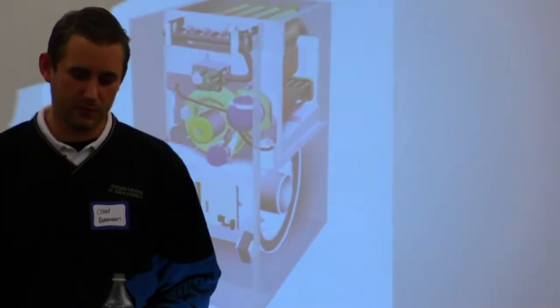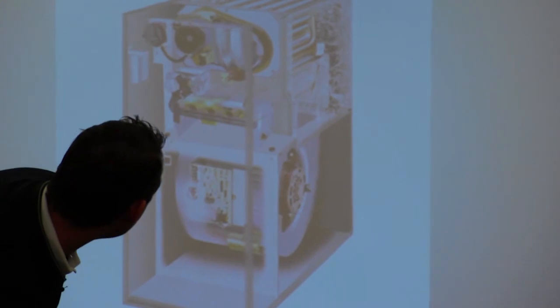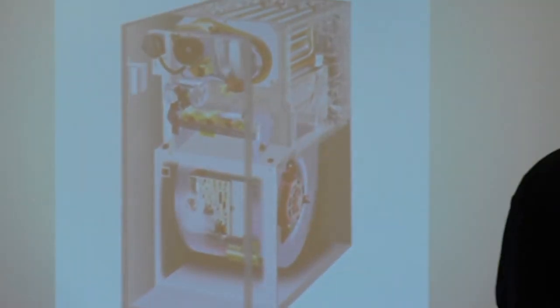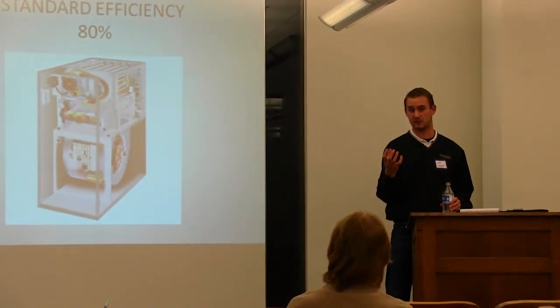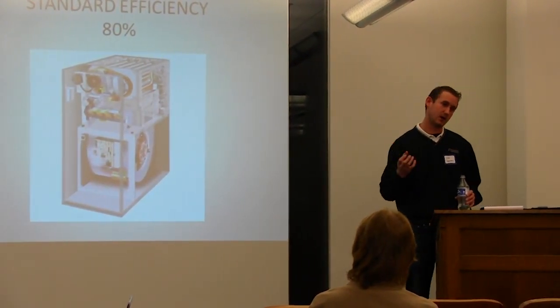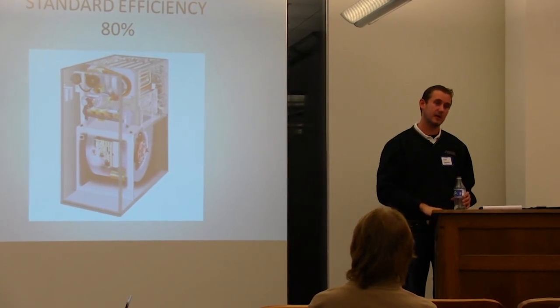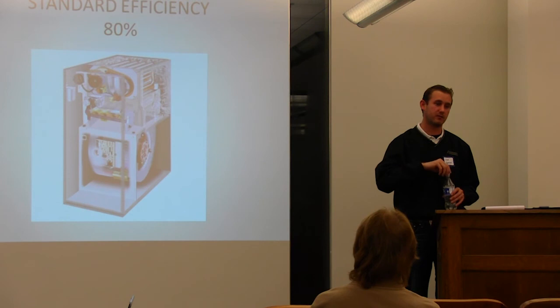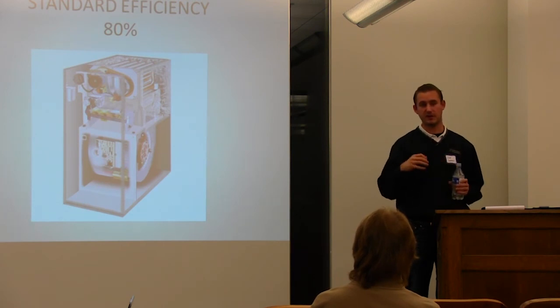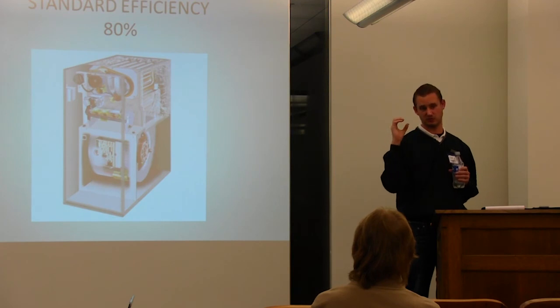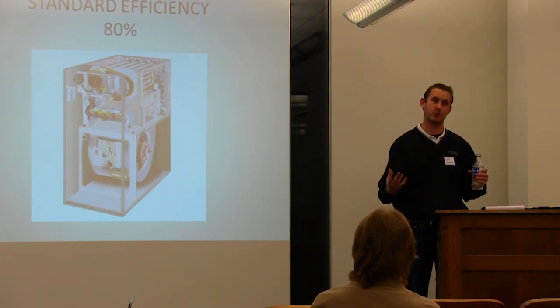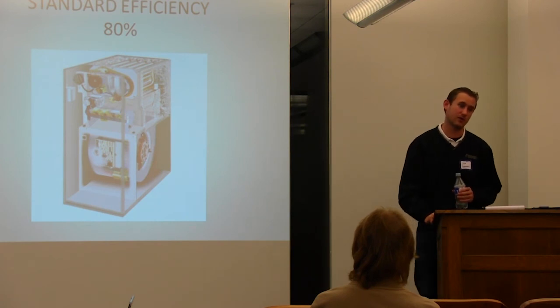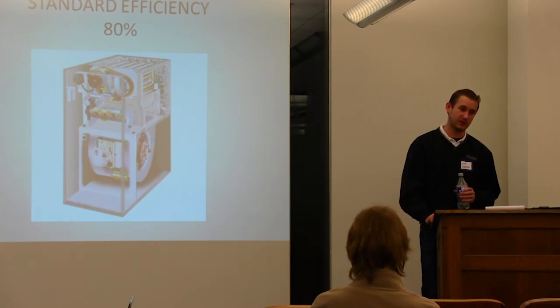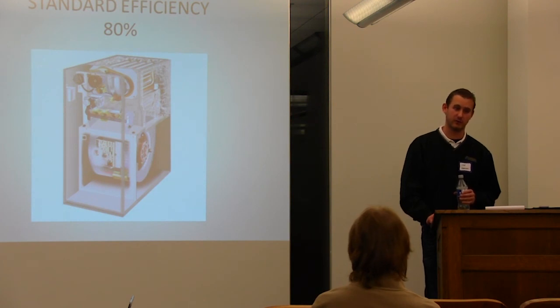That is the difference between an 80% furnace and a 90% furnace. An 80% furnace lacks a secondary heat exchanger, so only 80% of the heat is actually staying in the house. The other 20% is still very hot, and there's enough heat to carry it up and out of your house before it condenses. Whereas with a 90+% furnace, at 10%, there's not enough heat to get it out of the house, so it starts to condense as it travels through the pipes and creates water. You can't have water in a metal pipe, or else it's going to corrode out in about 2 years. That's why you see PVC venting with all new furnaces nowadays, because you have to account for the water.